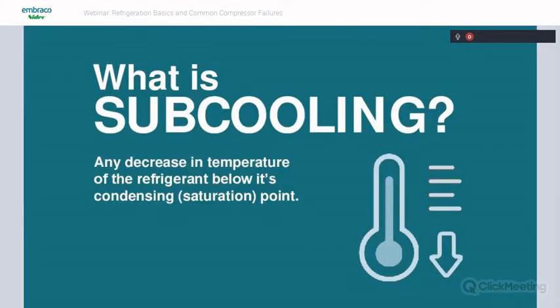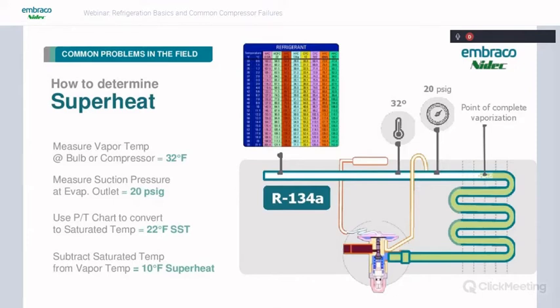And then there's subcooling, and that's any decrease in temperature of the refrigerant below its condensing or saturation point. So any temperature measured between the condensing point and a point in the system, you're going to call that subcooling. And we're going to use subcooling typically for systems with TXV valves. We'll talk a little bit more about TXV valves in a second. So when we're checking superheat, I apologize that we show a TXV valve here, but you can check superheat on a TXV valve to make sure it has the correct superheat. In commercial systems, there's a lot of TXV valves that require adjustment, and you may have to set superheat on a TXV valve. But basically, what we're going to do, we're going to check our low side suction pressure.